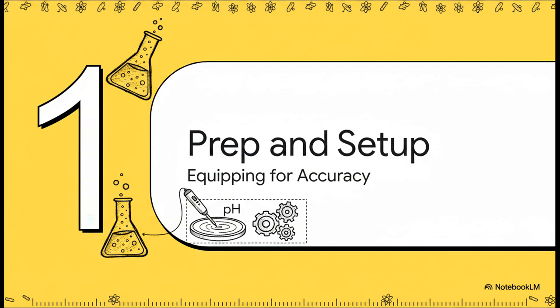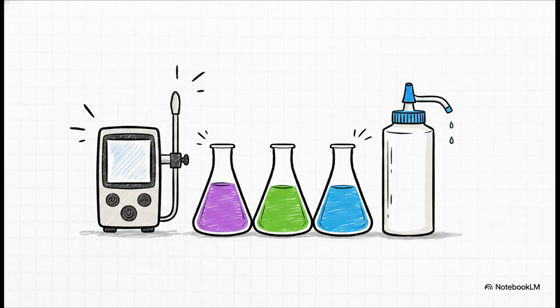Section 1. Preparation and setup. Equipping for accuracy. So prep is incredibly straightforward, but it is absolutely non-negotiable. You've got to gather your digital pH meter, your 3 specific buffer solutions, so that's the 4.0, the 7.0, and the 9.2, and honestly, plenty of distilled water. Having all of this staged right in front of you before you begin, like a chef's mise en place, prevents you from having to scramble mid-calibration. Because scrambling leads to dried-out electrodes and completely flawed data.